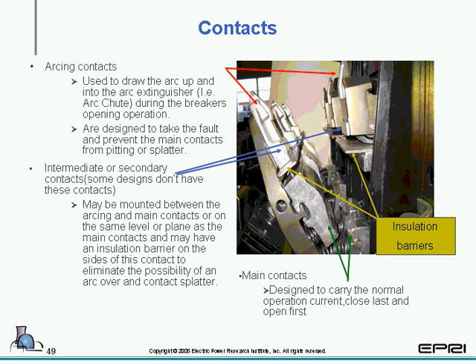And both the intermediate arcing and the arcing contact are designed to protect the main contacts, which are designed to carry the normal operating current, close last and open first on all designs. Main contacts will always close last and open first.